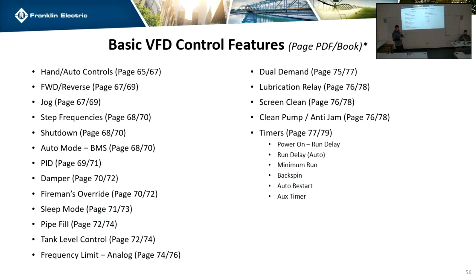Sleep mode, the pressure boost, that's purely pump application. The sleep mode part of HVAC is what I just talked about. We can wire a relay in so it goes to sleep based off of an analog signal. If you guys are interested with the water systems, the drive can boost the pressure. So if you're running at like 50 PSI to maintain water pressure, but the system is leaky and you don't want it to turn on every 5 or 10 minutes, it'll actually boost up another 5 or 10 PSI to go to sleep, so that you've just got a little bit more padding so the drive's not constantly turning off and on.